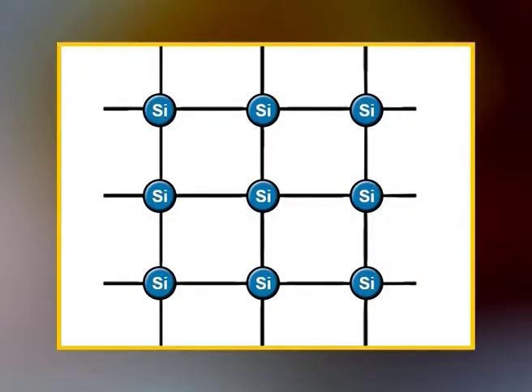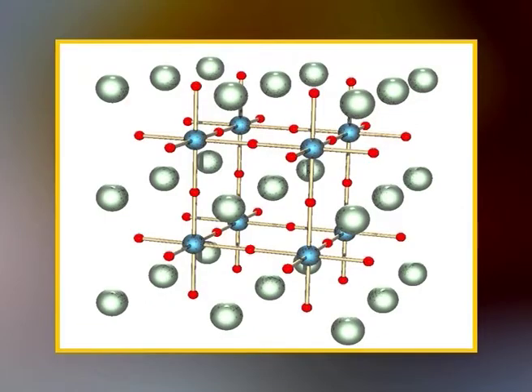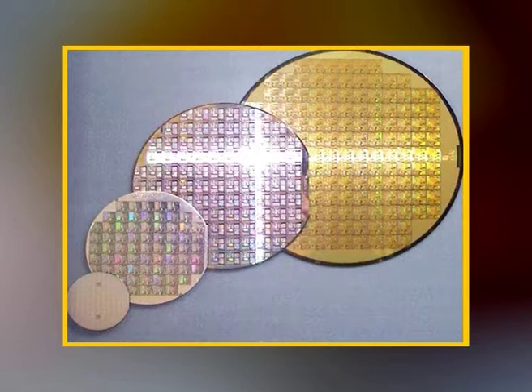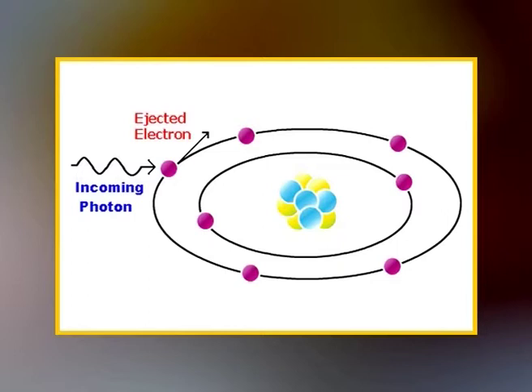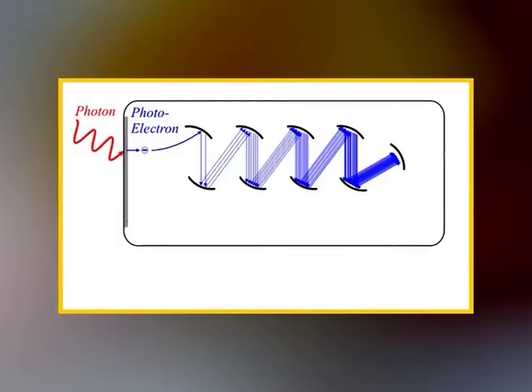Detectors have historically been based on silicon semiconductors in the form of lithium-drifted silicon crystals or high-purity silicon wafers. These work on the principle of photoionization, in which the entering X-ray photon interacts with the active detector material producing a number of electrons. The current produced by these electrons is converted to a voltage pulse by a capacitor and a resistor, so that each entering X-ray photon produces a digital voltage pulse. An ideal detector should possess three important qualities: sensitivity, proportionality, and linearity.